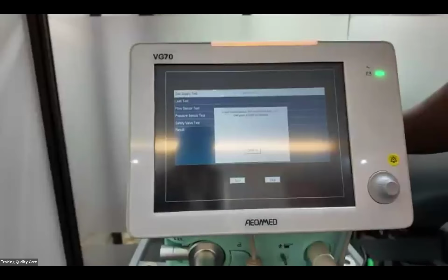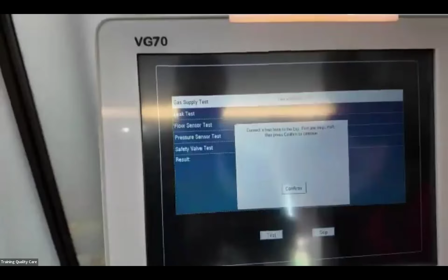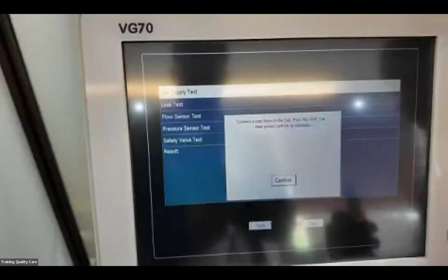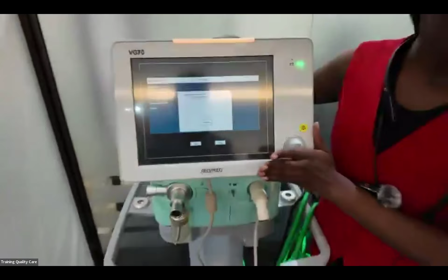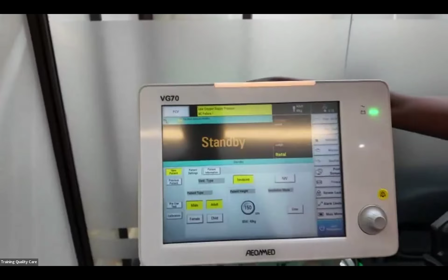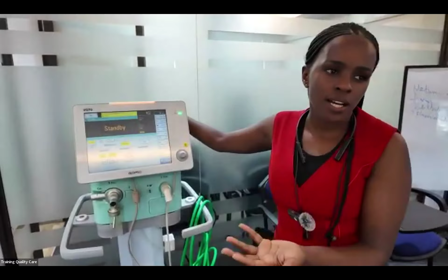I'll advise before you use the ventilator, just ensure that you test it. The test is for the leak test. We have the flow sensor test, the pressure sensor test, safety valve, and once it has passed, now you can confirm and proceed. I'll skip because I am not connected to the oxygen, so the ventilator is going to fail. So I can skip that. Now I have skipped. Now I move to the settings. We're assuming that we've passed the test.